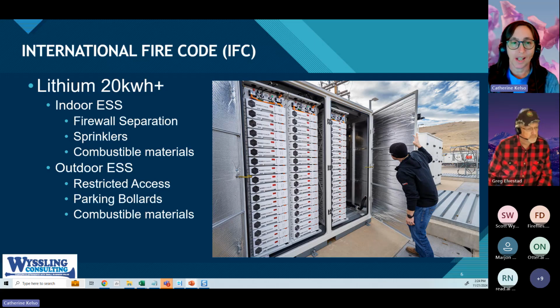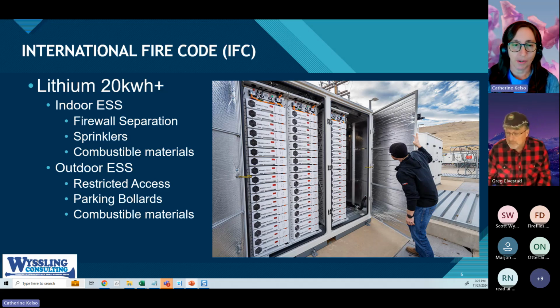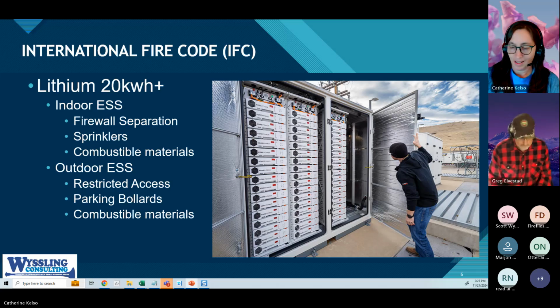So the solution is to put the batteries outside. Now all we have to worry about is restricted access—very simple. A smaller battery cabinet can just be locked; a larger system just needs a fence around it. We also have to make sure that if we're near a parking lot where vehicles could hit it, we've got parking bollards. We still have to keep it away from combustible materials—easy not to set a gas can next to it, but you also have to look at trees, dumpsters, and other things nearby so we don't have combustibles too close to the battery system.